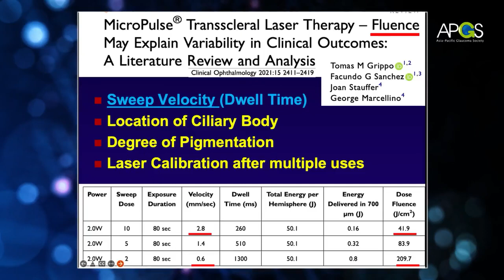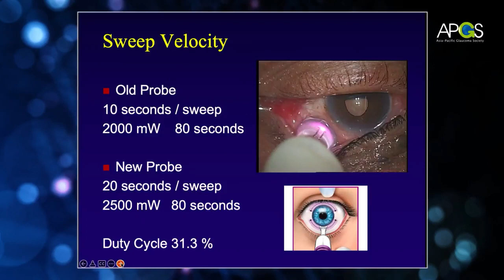And this has often been an issue: how fast do you run this probe? With the old probe, it was supposed to be 10 seconds per sweep. But with the new probe, it is supposed to be 20 seconds per sweep with the increase in energy. And so the velocity at which you run this probe actually determines the major efficacy of this technique. And I think ideally you should be using a stopwatch when you do this micropulse laser.